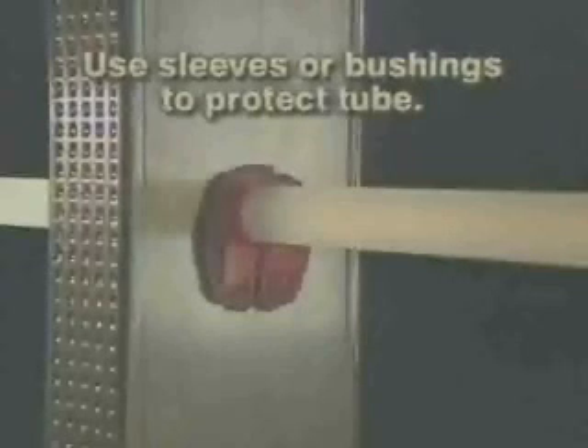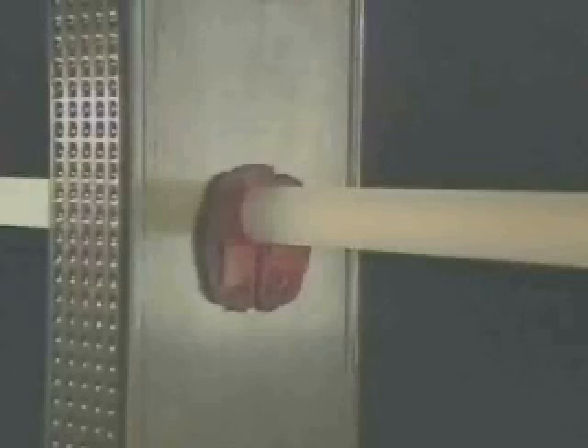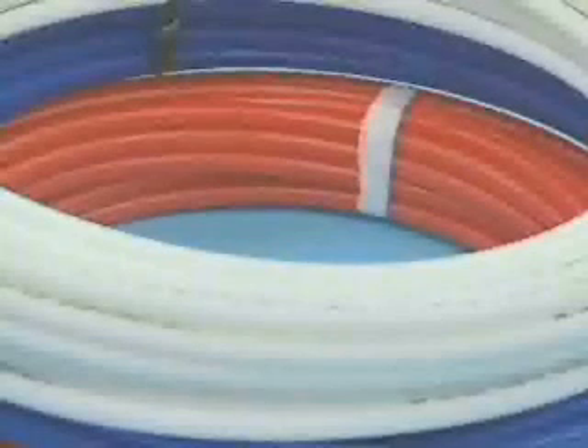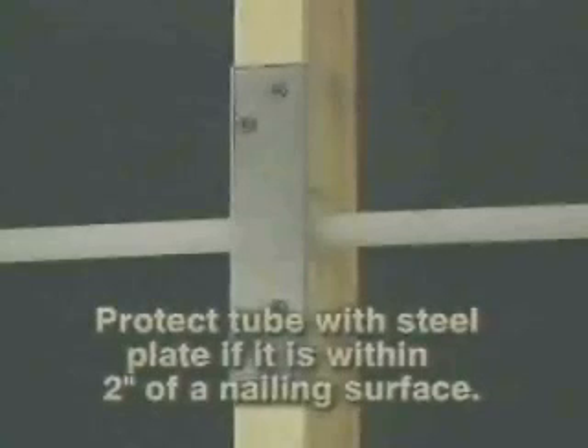Use sleeves or bushings for the tube when it penetrates metal studs. Bushings are not required when penetrating wood or particle board when the hole is at least 1⅛ inch larger than the tube and the tube is not restricted. PEX, like copper or other plastics, can be punctured by a nail. For this reason, the tube should be protected with a steel plate if it's within 2 inches of a nailing surface on a stud, plate, or joist.